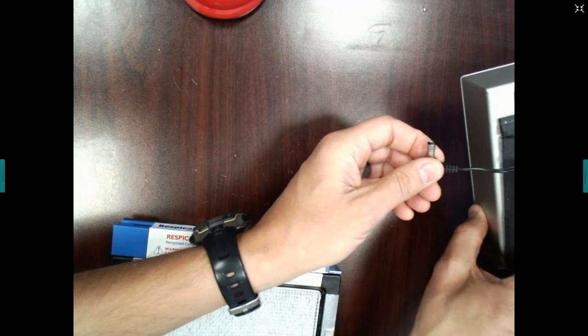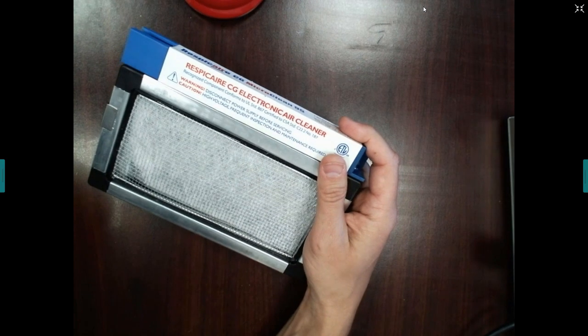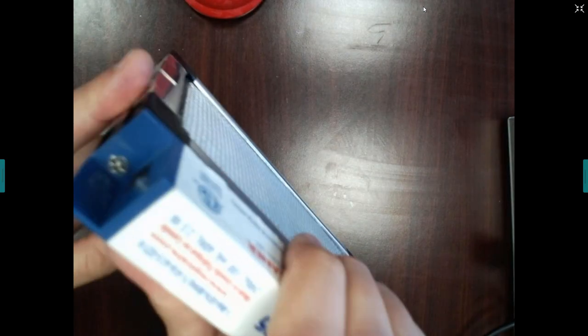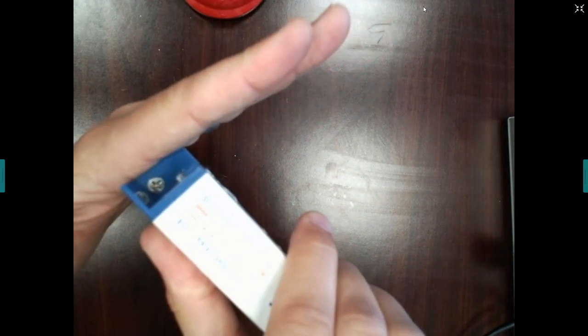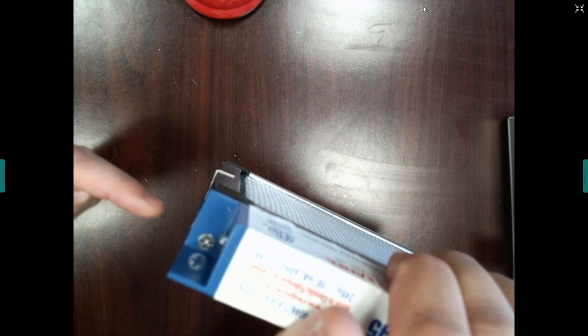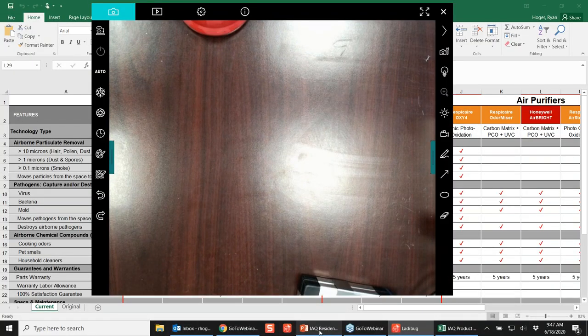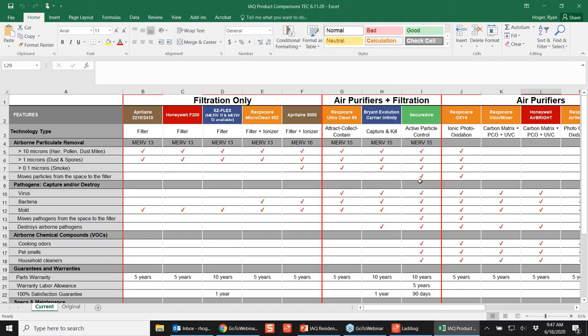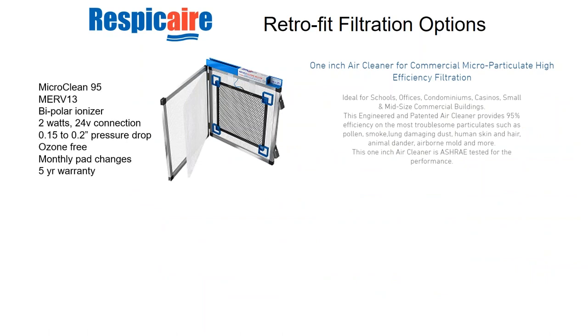There's also a two-inch commercial version. Power connection is just a small low-voltage plug — you plug it into the same outlet as your humidifier and slide it into your existing one-inch rack. Pro tip: put a little foam tape on the sides so the door seals it properly and prevents bypass air. Any filter bypass is bad, but the better the filter, the more air will bypass through even a small gap. This unit has under 0.2 inches of pressure drop, consumes only 2 watts, and carries a five-year warranty. There's no reason not to offer this to anyone with an existing one-inch filter rack.